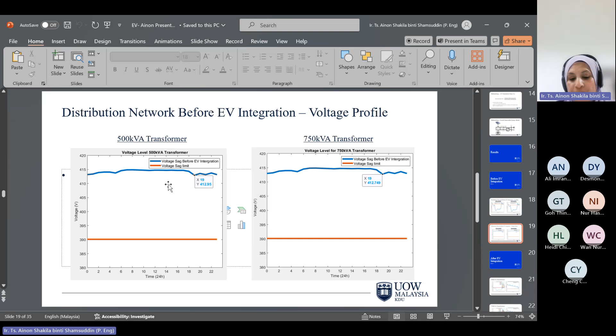Then we also check the voltage profile. The graph shows the maximum voltage sagging of the 500 and 750 kVA transformers during the peak hours drops to 412 volt, which occurs at 7 p.m. The voltage is supposed to be 415, the three-phase voltage, but during the peak hours it dropped to 412, especially at 7 p.m. During off-peak hours, the voltage level recovers. Even though it dropped to 412, it is still maintained within the TNB acceptable limit, because the TNB limit is 6% voltage drop. So it's still under the limitation of TNB.